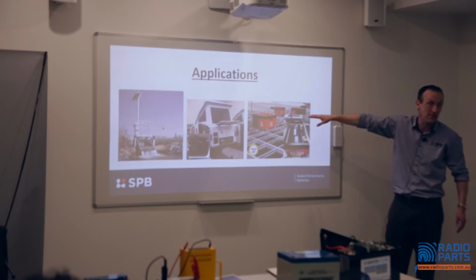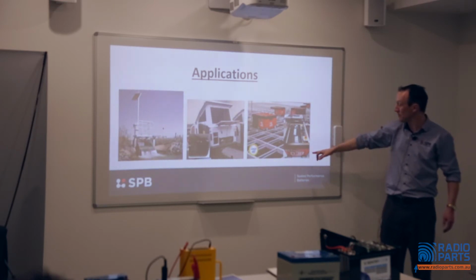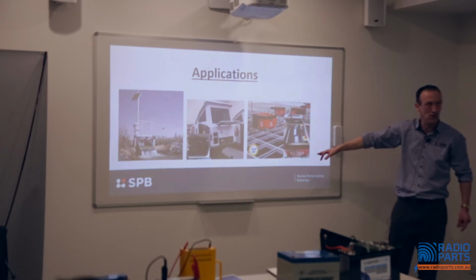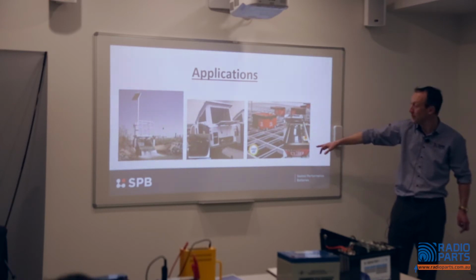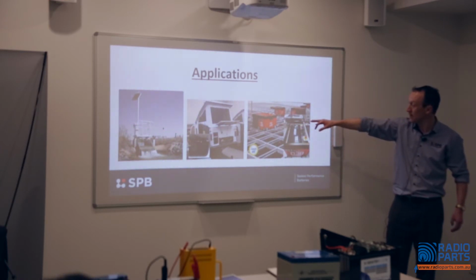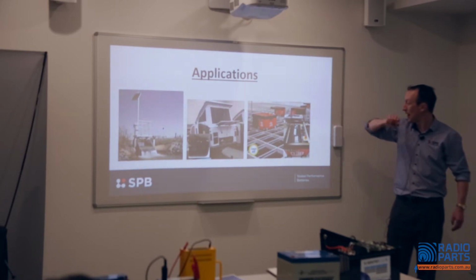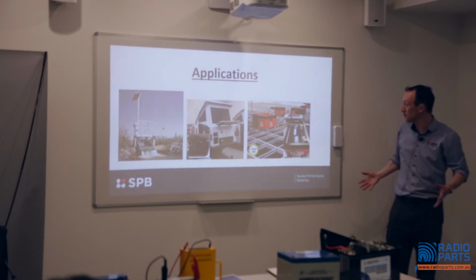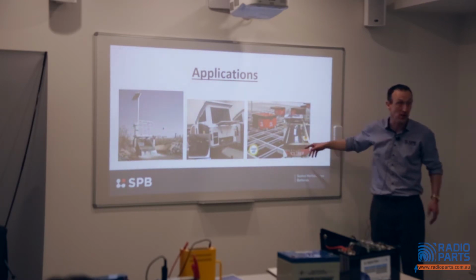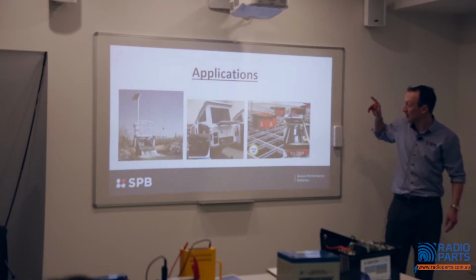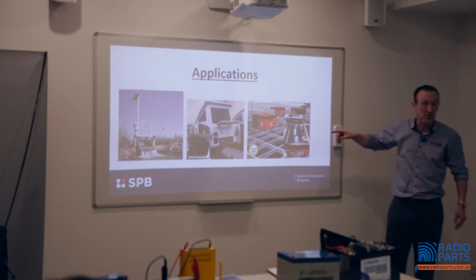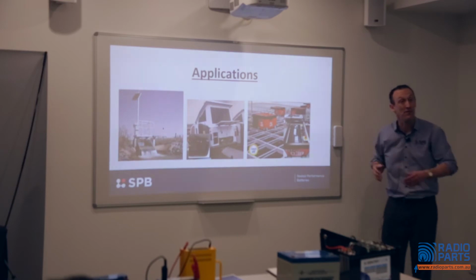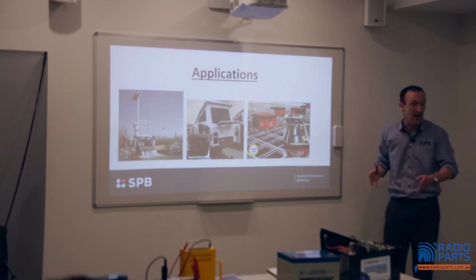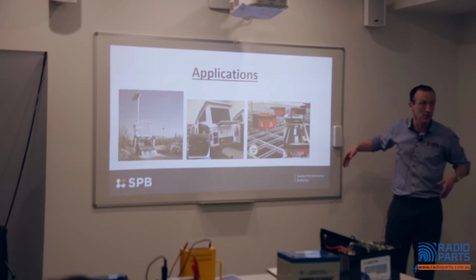Originally they were spec'd with lead acid. The company that does it is called Swisslog, an engineering company. They originally had lead acids in these, two of them in series, 24 volt. Part of the condition was that these units - 50,000 bucks a pop, they've got 70 of them - come with a 3-year warranty, and when you replace the batteries you have to use their batteries, bought from them. They're lead acid, not efficient, and they gouge you like all hell, but after 3 years the warranty is finished on the whole lot and you can put in whatever you want.